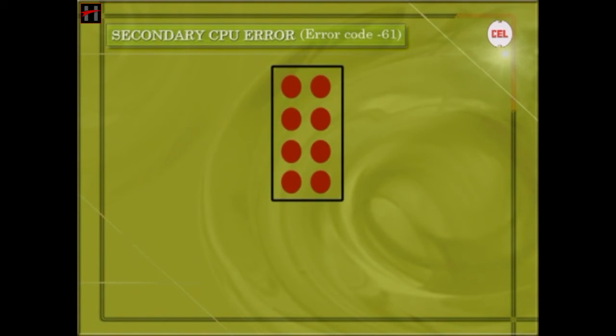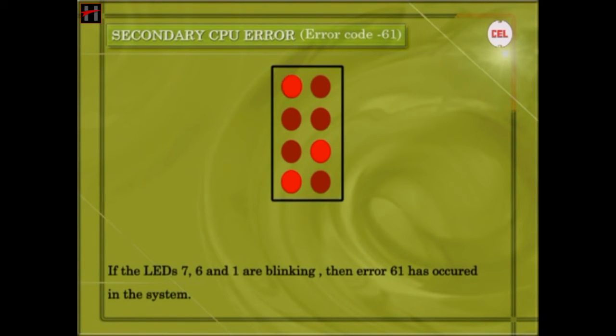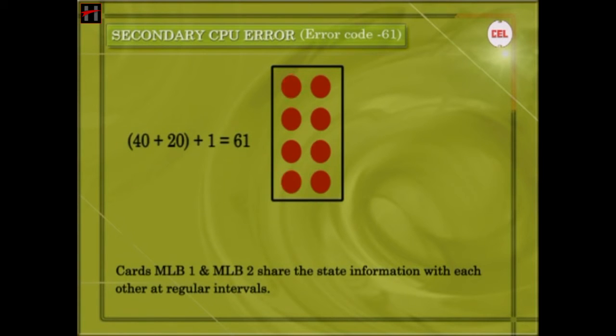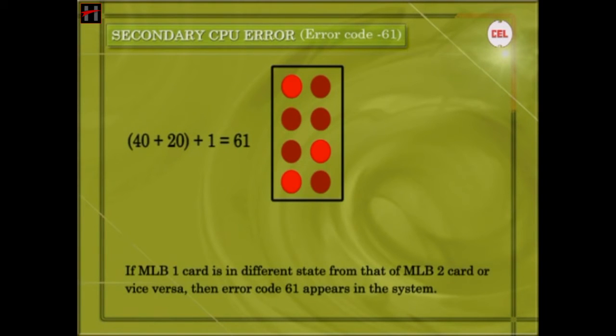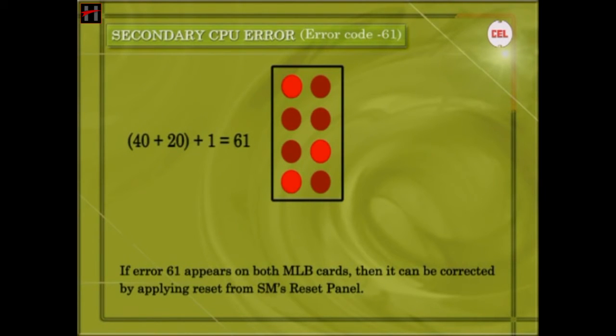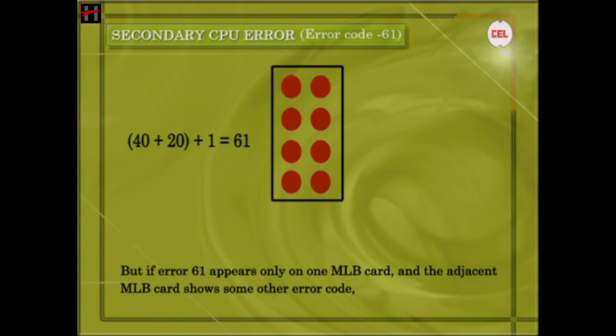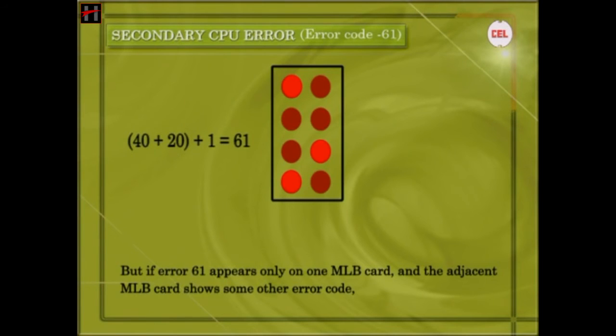Secondary CPU Error: If LEDs 7, 6, and 1 are blinking, then Error 61 has occurred. MLB1 and MLB2 cards share the state information with each other at regular intervals. If MLB1 card is in a different state from that of MLB2 card or vice versa, then Error 61 appears. If Error 61 appears on both MLB cards, it can be corrected by applying reset from the SM's reset panel. But if Error 61 appears only on one MLB card and the adjacent MLB card shows some other error code, then the rectifications to be followed will be that of the error code on the adjacent MLB card.